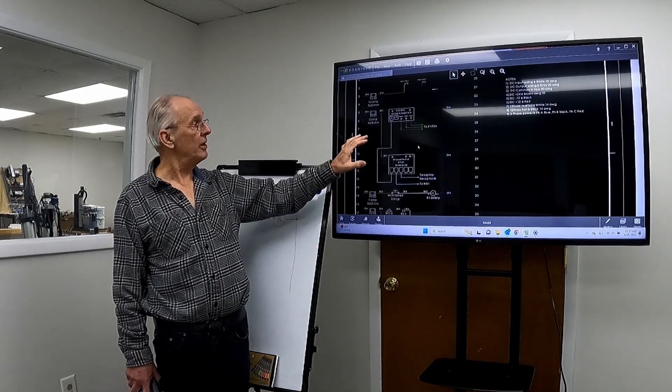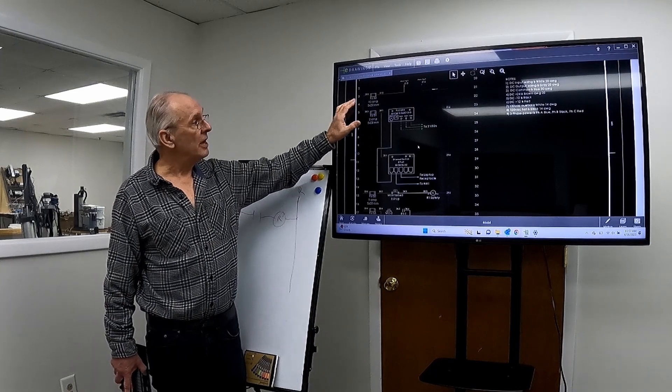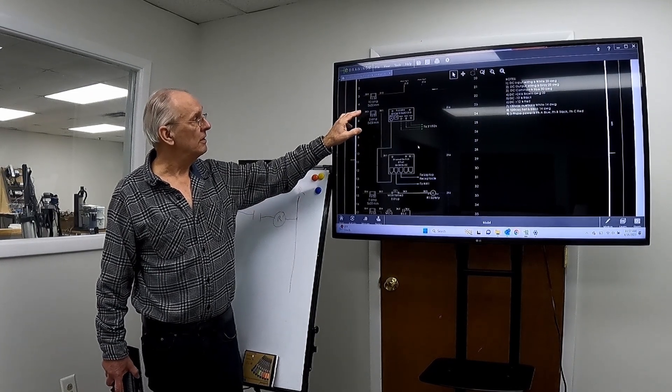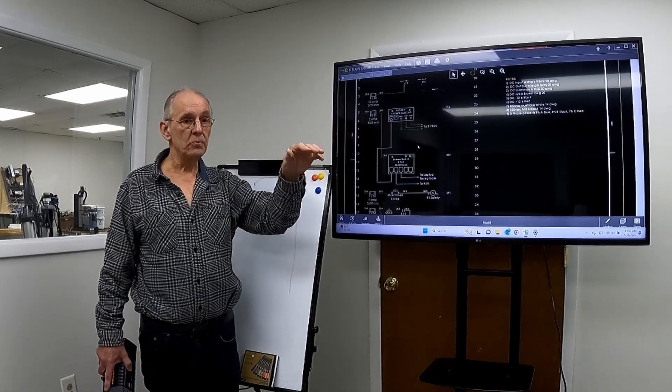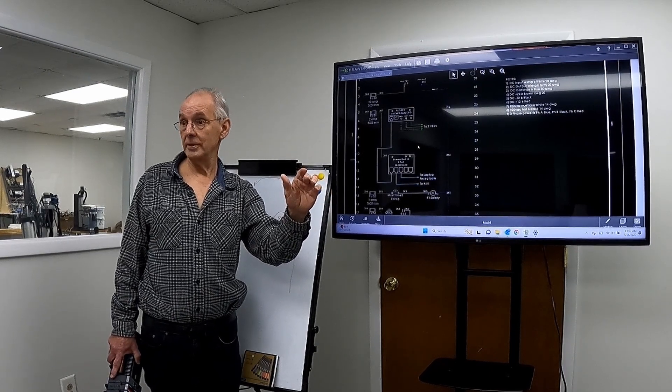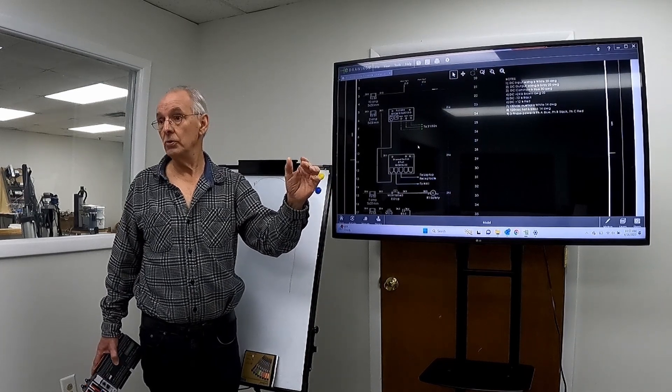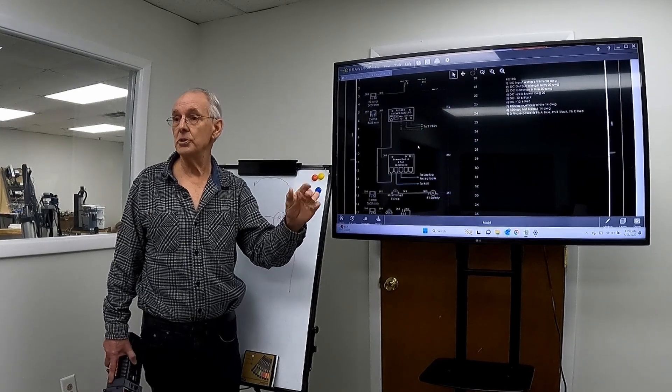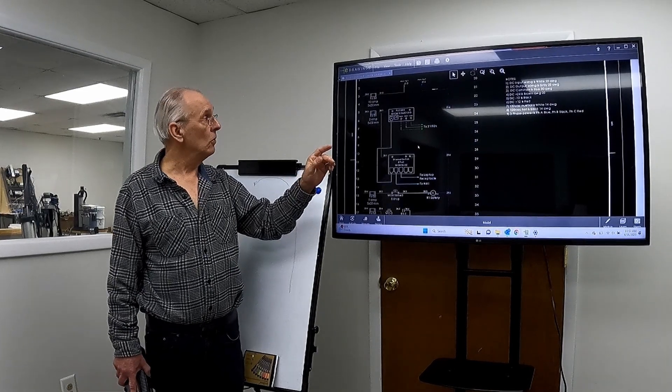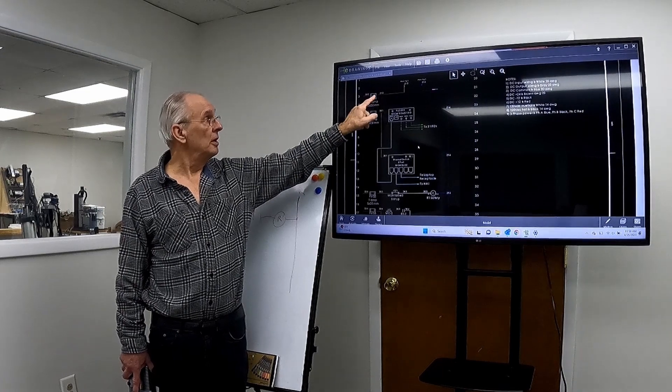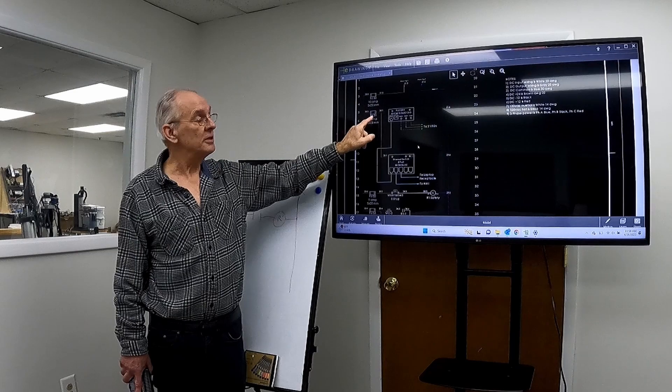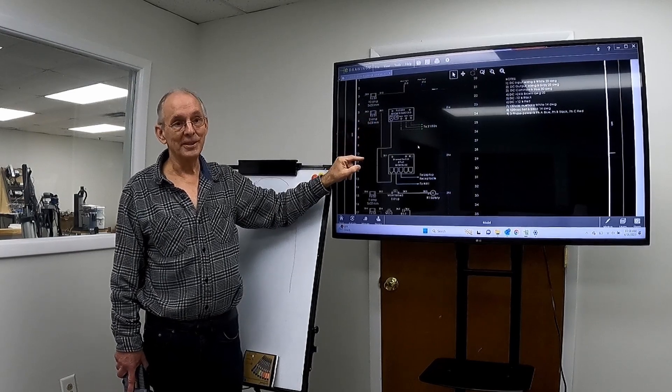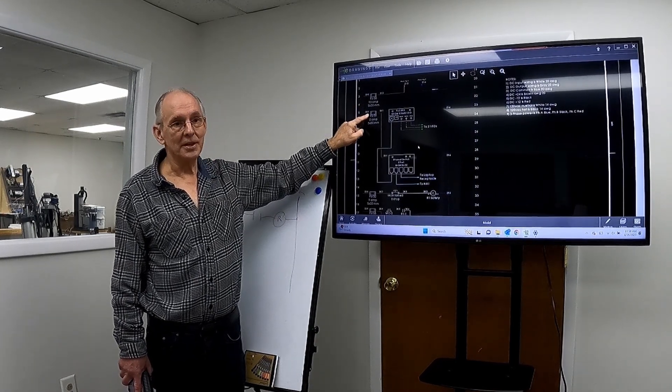So this is the exact same thing. And all right, so we have in every part of every circuit here, you're going to see there's always a first fuse. And so in wiring that, we come off the - you always feed the top of the fuses. You never ever feed power to the bottom of a fuse, right? And that's a safety issue because everybody expects the power to be coming in the top and going out the bottom. And so most things are designed that way. So, but this fuse - this is, so the power comes in the top of this fuse, but it leaves the bottom of this fuse. And then it loops over to the top. So this is the top of the next fuse, right? The bottom of the fuse here, top of the fuse on this side.